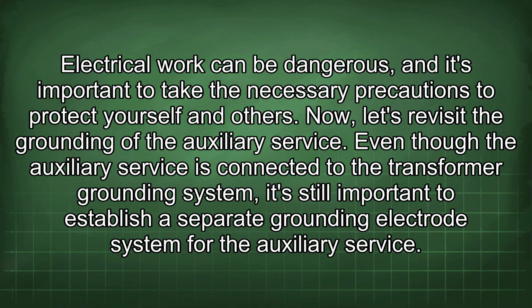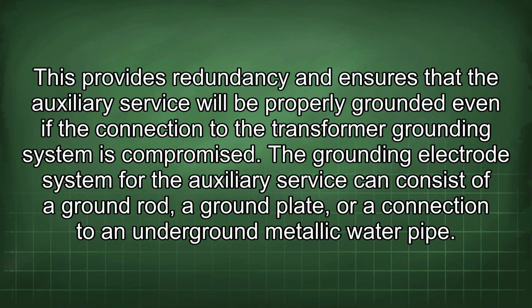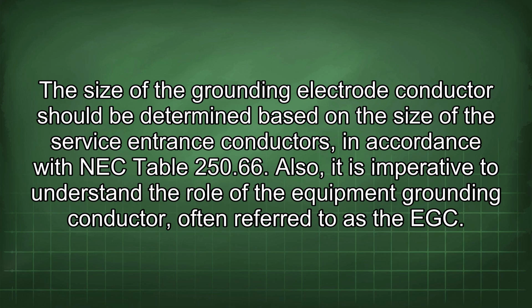Now, let's revisit the grounding of the auxiliary service. Even though the auxiliary service is connected to the transformer grounding system, it's still important to establish a separate grounding electrode system for the auxiliary service. This provides redundancy and ensures that the auxiliary service will be properly grounded even if the connection to the transformer grounding system is compromised. The grounding electrode system for the auxiliary service can consist of a ground rod, a ground plate, or a connection to an underground metallic water pipe. The size of the grounding electrode conductor should be determined based on the size of the service entrance conductors, in accordance with NEC Table 250.66.